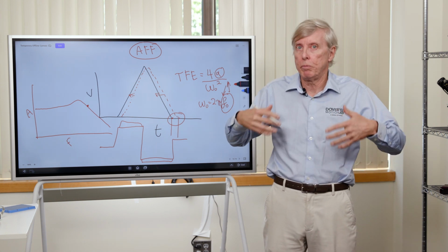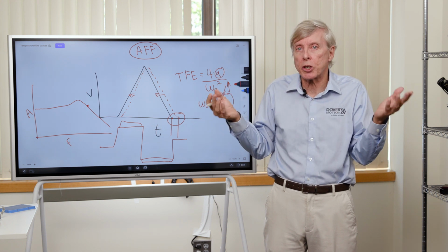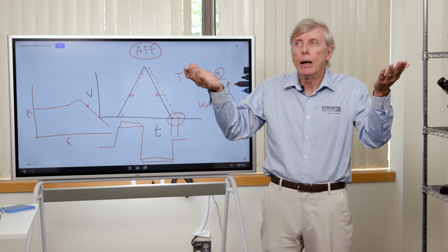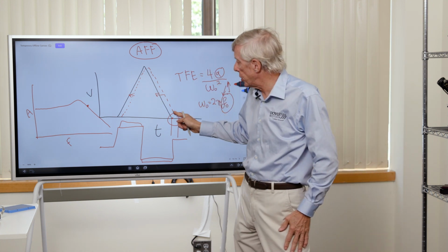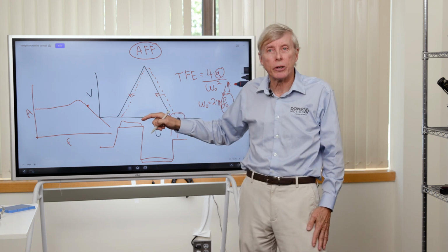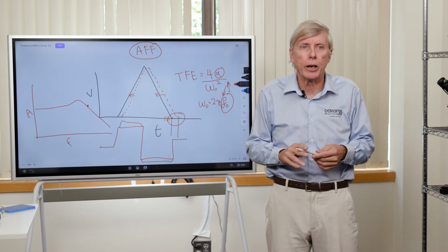That is true feedback. But in this case, it's feed forward, and it will not disturb the stability of the system. Now, as you increase the acceleration feed forward, things get better and better, and this gets smaller and smaller. And then if you put in too much, it begins to go the other direction. And then you know to back off and put it at that sweet spot right in the middle.